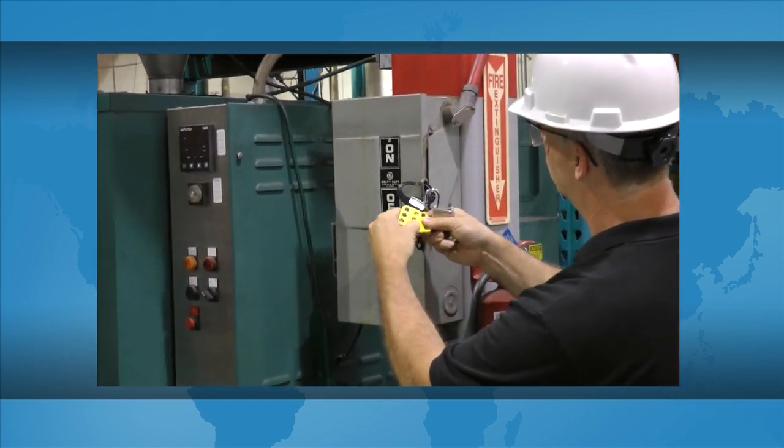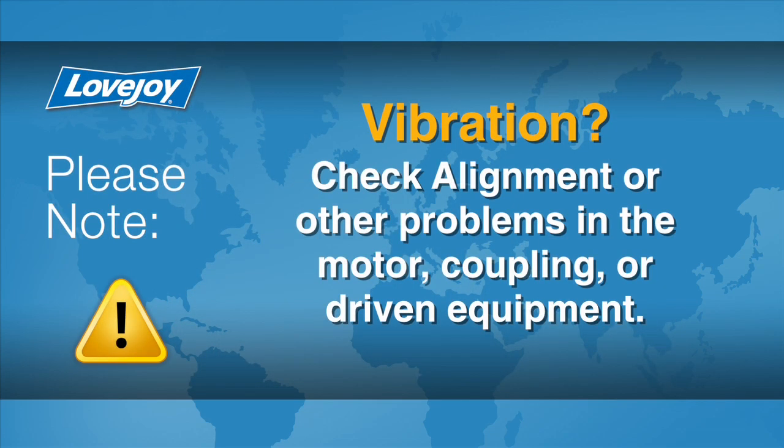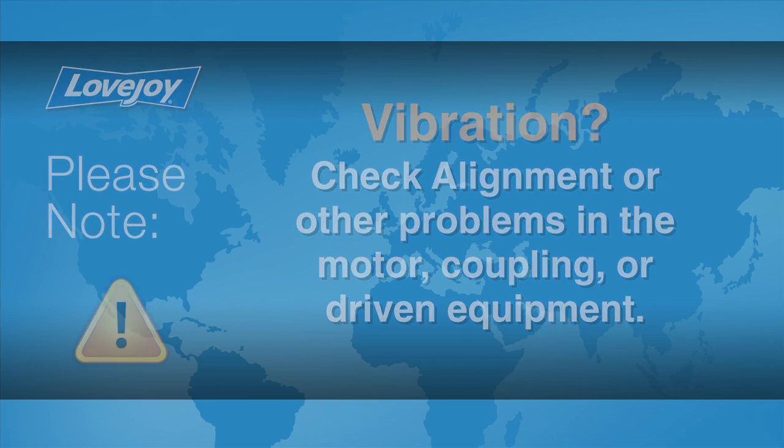The equipment can then be started up and tested. The coupling and equipment should run smoothly. If vibration is detected, it could indicate that there is an issue with alignment or other problems. These could exist in the motor, coupling, or driven equipment and should be resolved prior to placing this coupling into operation.